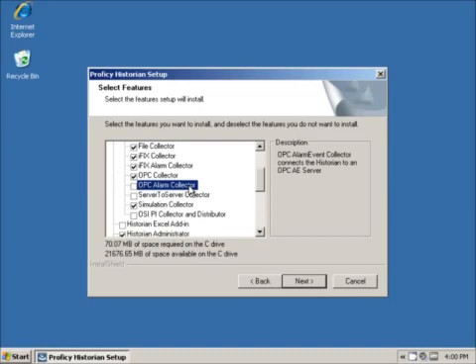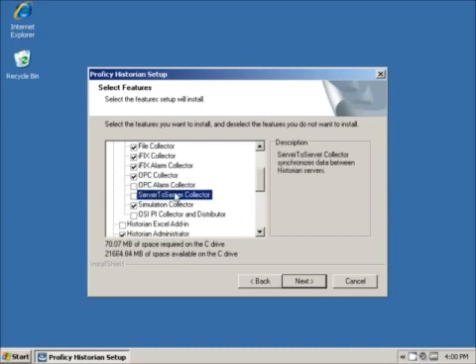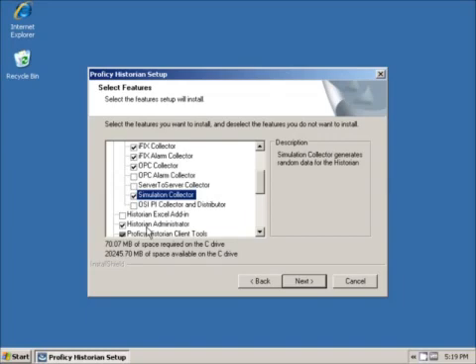The OPC Alarm Collector is a generic OPC A&E Collector with similar capabilities to the iFix A&E Collector. The Server-to-Server Collector is another transformation collector, but with the source on one Historian server and the destination on another. This is a licensed option and is included in the Enterprise license. The Simulation Collector is used for generating simulation data in the Historian, and is not required for production systems. I will deselect it.